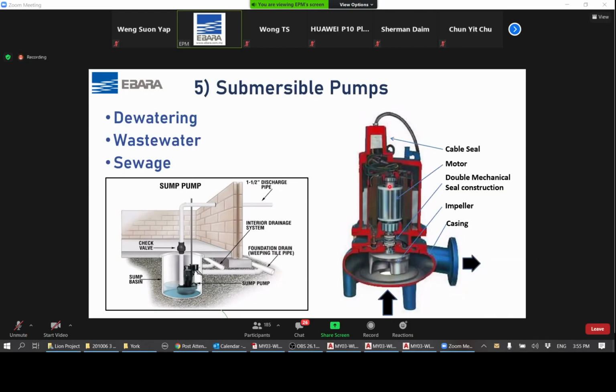And on top there will be the cable entry, where the wiring of the power cable will come out. Even this is a very important design element, where a lot of pumps have died or been damaged because of a leaking cable seal. In the coming sessions.